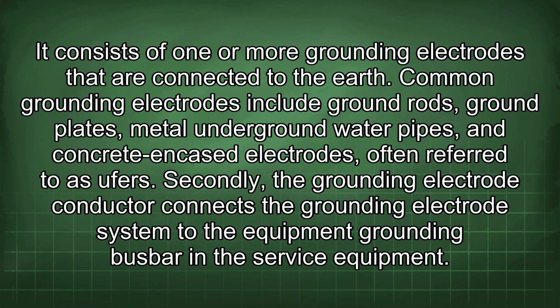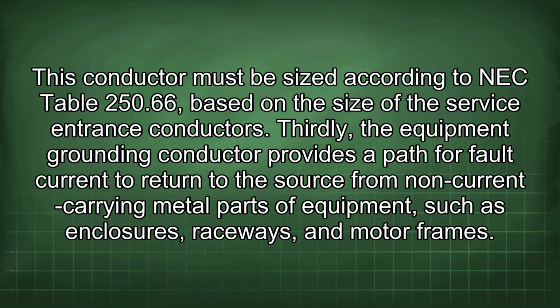Secondly, the grounding electrode conductor connects the grounding electrode system to the equipment grounding busbar in the service equipment. This conductor must be sized according to NEC Table 250.66, based on the size of the service entrance conductors.